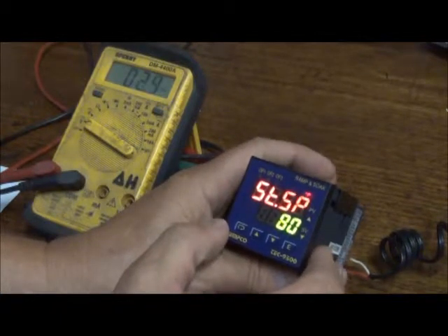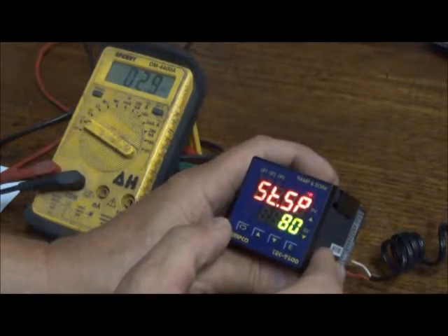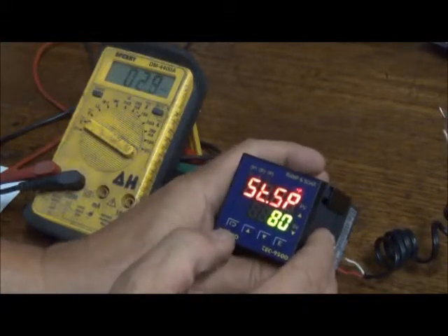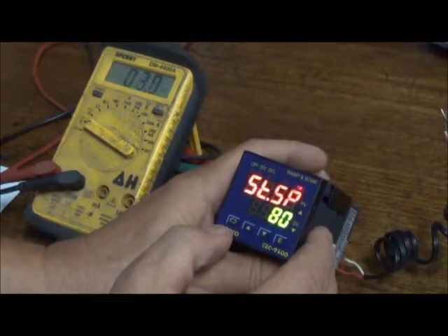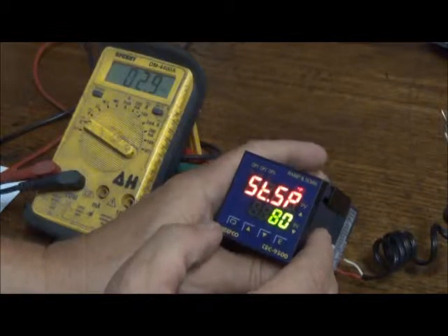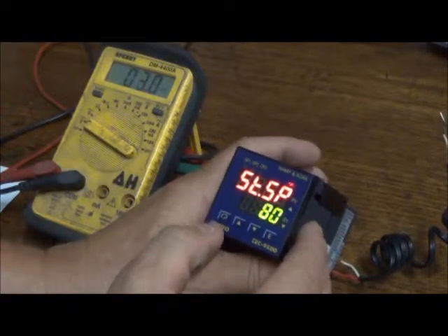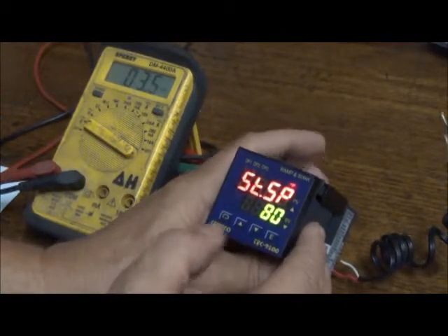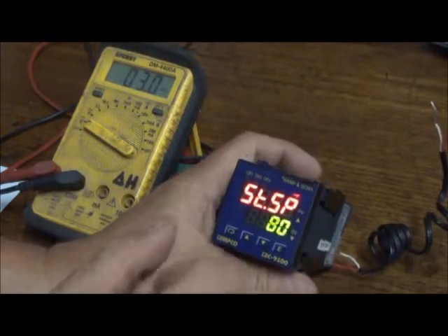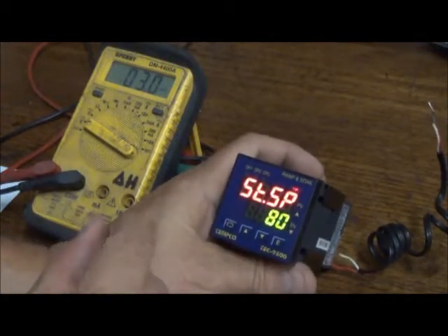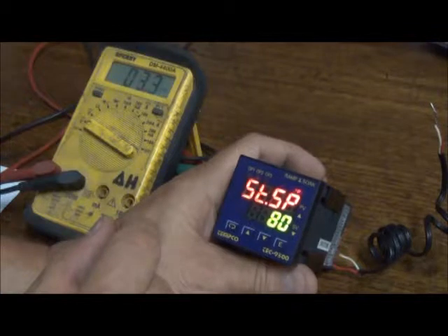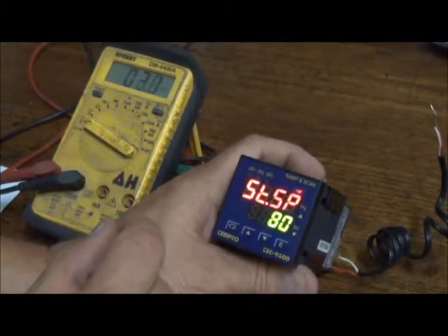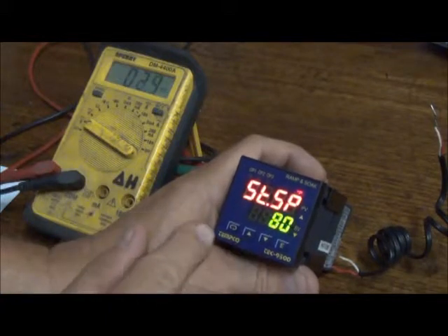Maybe you have a heavy load in your process, and that can enable you to do that. Whereas other times you may have a very light load, the temperature recovers very quickly and keeps up a little bit. It's like a guaranteed soak function. So hold back gives you the ability to make sure that your process catches up to the programmable control cycle before you go into a soak time, so you're guaranteed to have a soak.